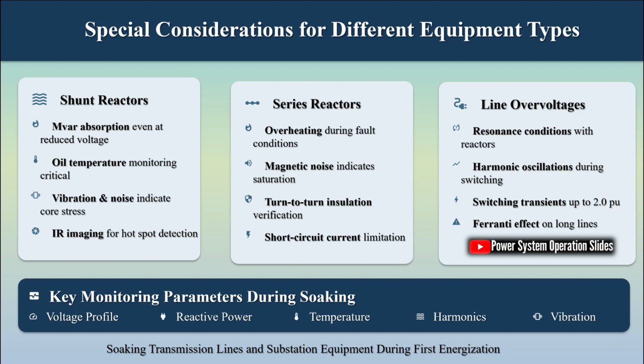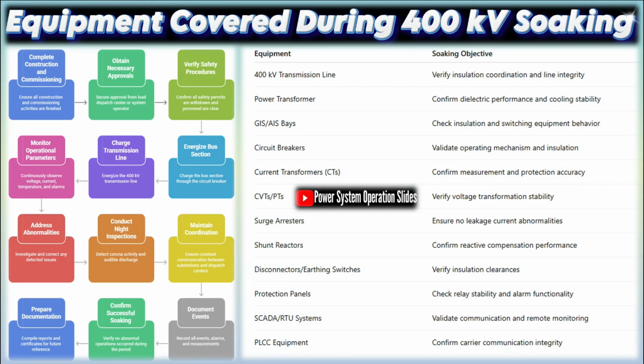While factory acceptance tests and routine commissioning tests provide valuable information, they may not reveal every defect or weakness that exists within the equipment. The soaking process provides an additional layer of assurance by exposing the equipment to sustained electrical stress before it is connected to the full power system and subjected to operational loading conditions.